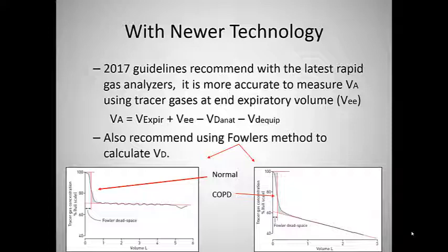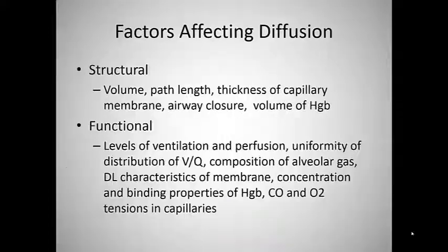They're going to be incorporating that into the software and equipment within a couple of years, but it's not there in most systems yet. That's one of the new changes instead of the calculation, and it will be more accurate than what we're doing now. For people with bronchiectasis, lobectomies, tracheomalacia, or dilated airways, the calculations we use now can alter your alveolar volume by as much as 10, 15, even 20%.